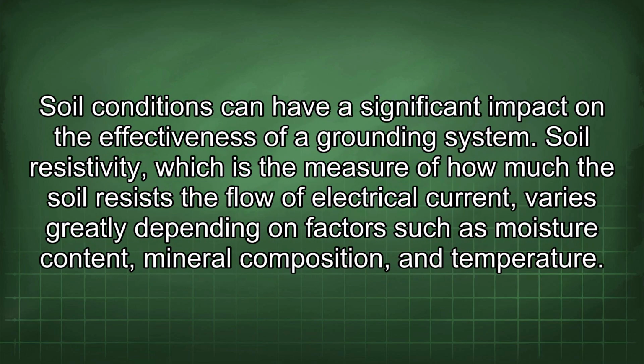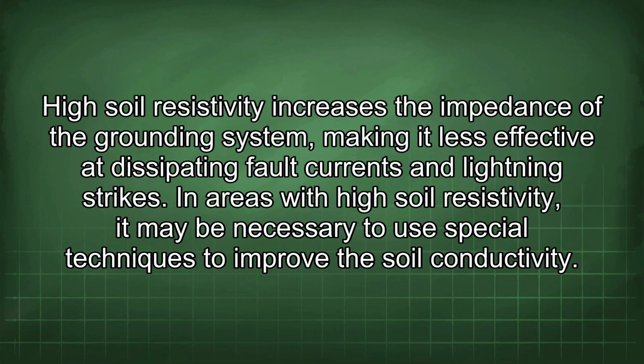Soil conditions can have a significant impact on the effectiveness of a grounding system. Soil resistivity, which is the measure of how much the soil resists the flow of electrical current, varies greatly depending on factors such as moisture content, mineral composition, and temperature. High soil resistivity increases the impedance of the grounding system, making it less effective at dissipating fault currents and lightning strikes. In areas with high soil resistivity, it may be necessary to use special techniques to improve the soil conductivity.